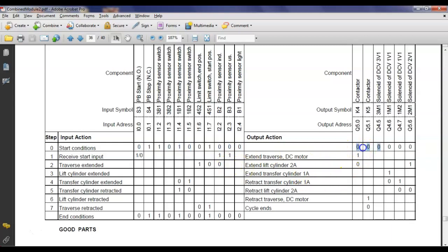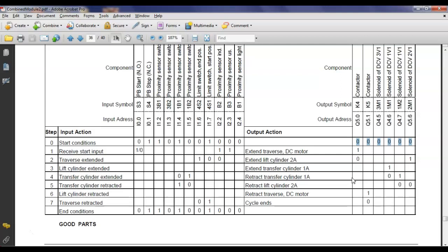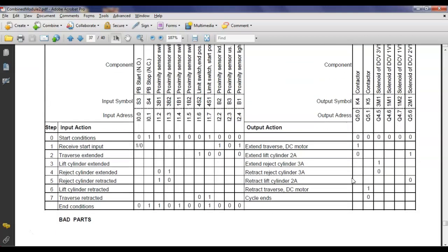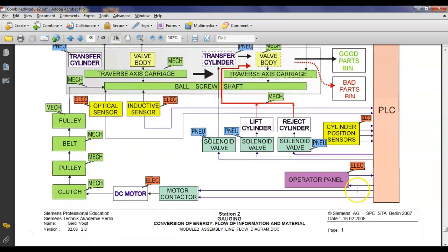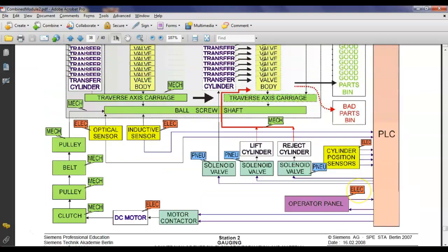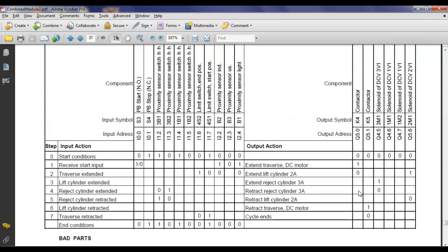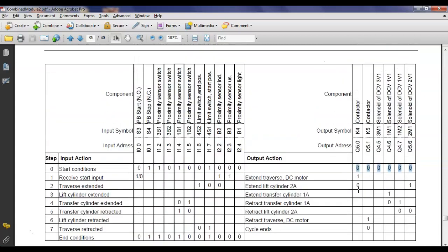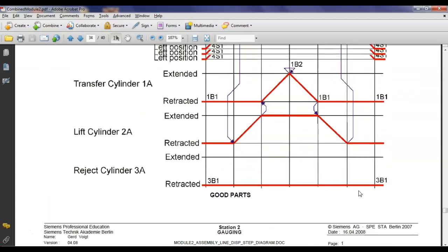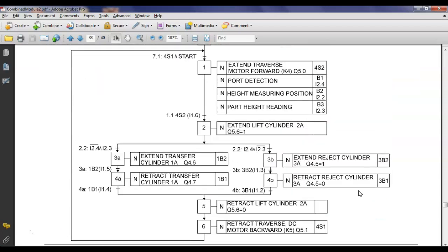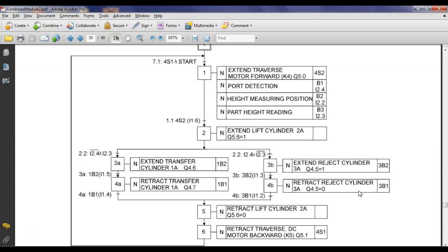We'll go back and review that. Okay, so that's interesting. That's a really good chart to find right off the bat. This we've never used. The 3 main things that you would use to try to figure out where it's stalling are either your step chart or your function chart.